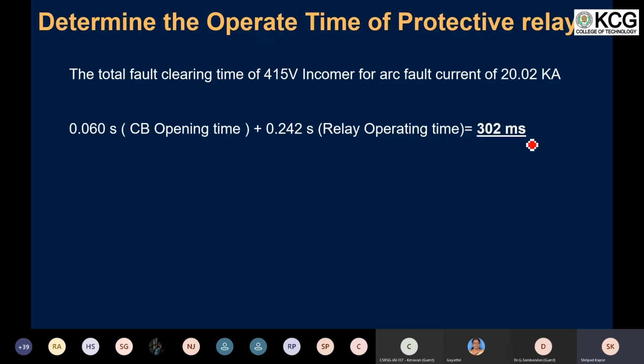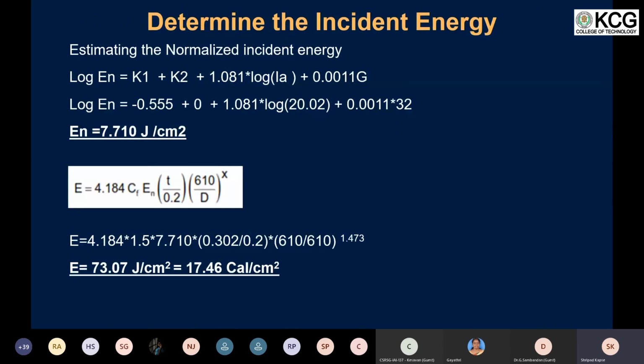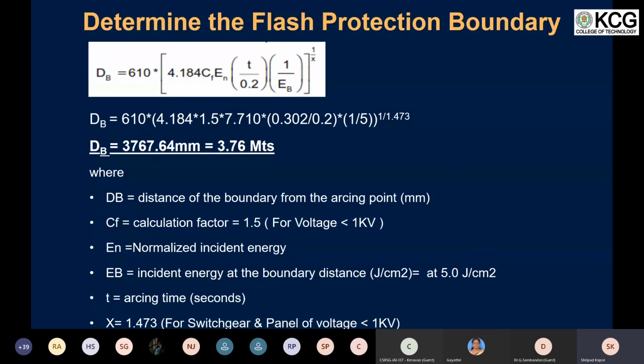And considering this 302 millisecond as overall fault clearing time, we determined the incident energy, which would have been the worst case incident energy, coming to about 17.46 calorie per centimeter square. And using that incident energy, we determined the boundary of an arc flash here, which was coming to be around 3.76 meters.